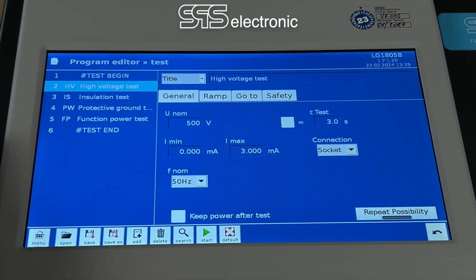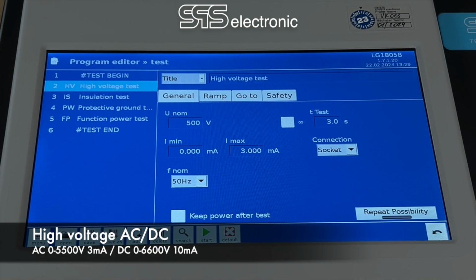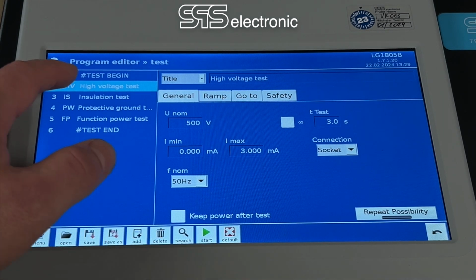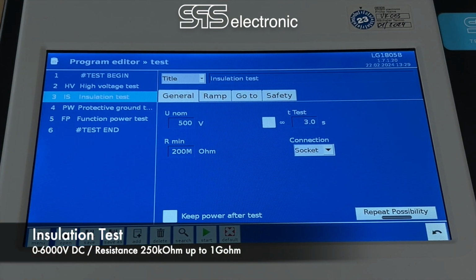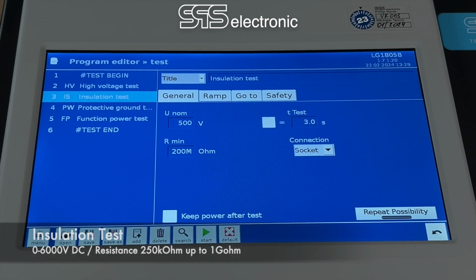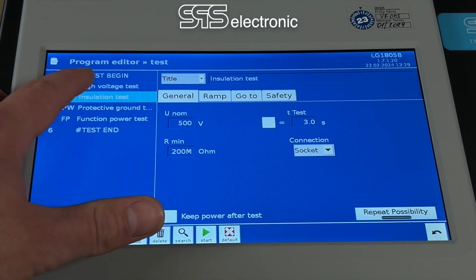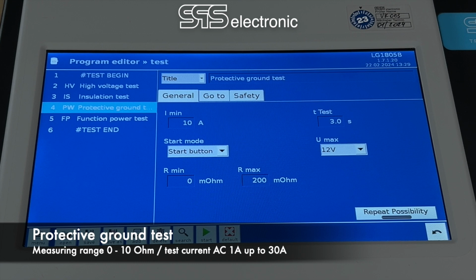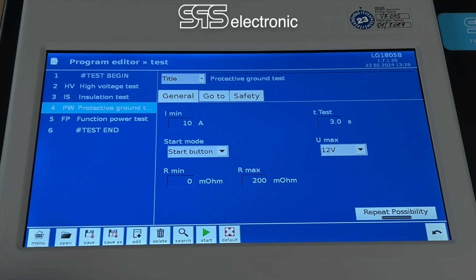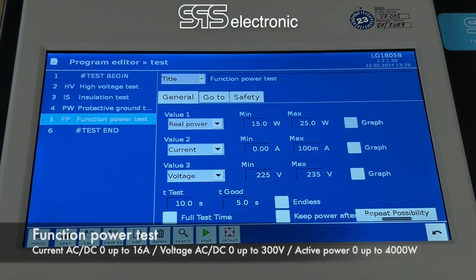First step is high voltage test, where you will set up voltage, current, and test time. Next step is insulation, where you will also set up voltage, test time, and minimum resistance. Third step is protective wire test, where you will set up minimum current, test time, and range of resistance.